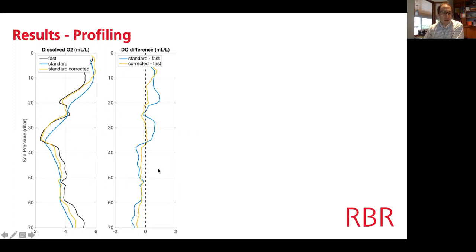And so we started looking at how we could correct the 8-second time constant sensor to better fit the fast sensor. What we have here is the fast data, as you would expect, in black. We have the blue data, which is the same as what you saw before, the raw 8-second time constant sensor. And then we've gone through and done a correction algorithm, or a tightening algorithm, that will simulate a faster response. That's what we have for the corrected yellow here, which means we're able to correct the 8-second time constant sensor to provide a little bit better simulated resolution.